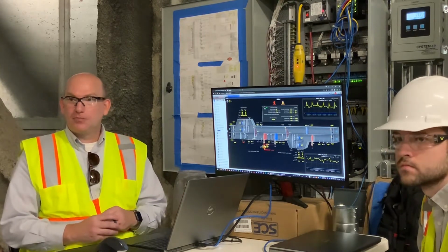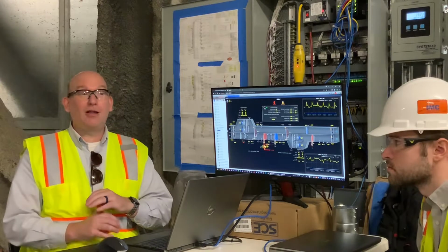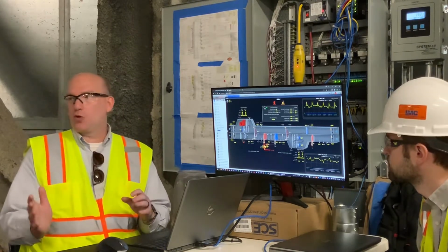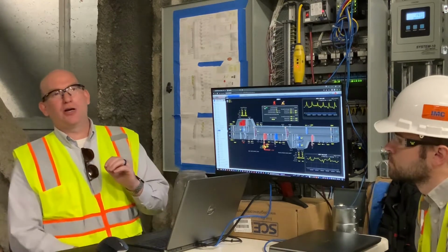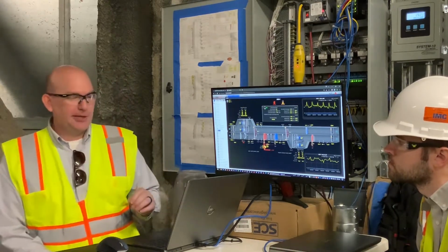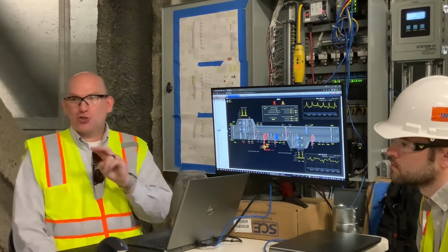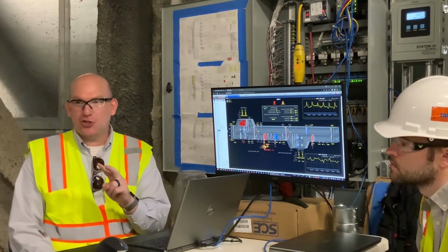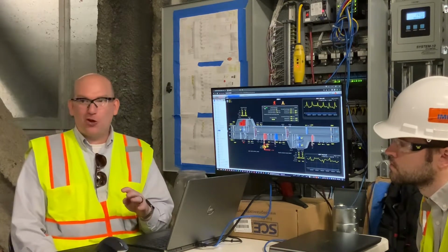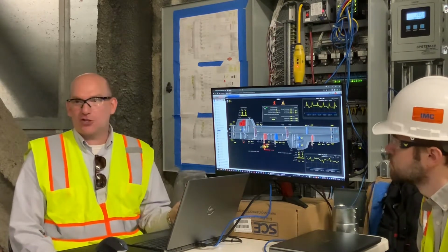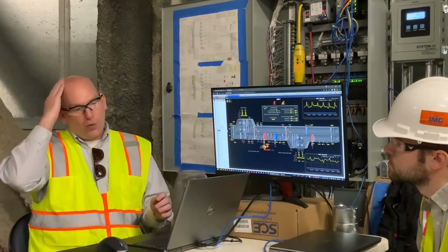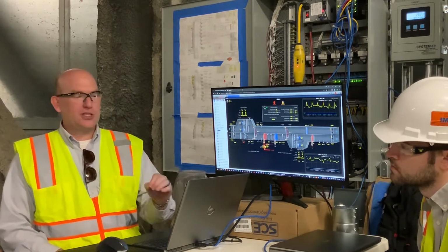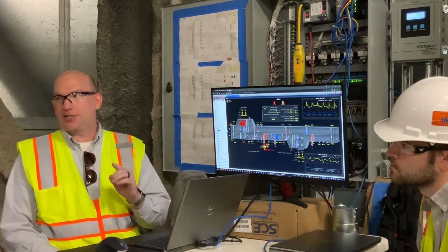Those run on static, which is based on a large number of sensors out in the space. The reason there are so many more than we would normally see is because there has to be redundancy. Each air handler has 2 remote sensors associated with it. So if there are 4 air handlers and each has 2, that means there's 8 total on the supply and 8 total on the exhaust. What we look at is the worst case scenario in the building, and we control the duct static pressure to that worst case scenario.